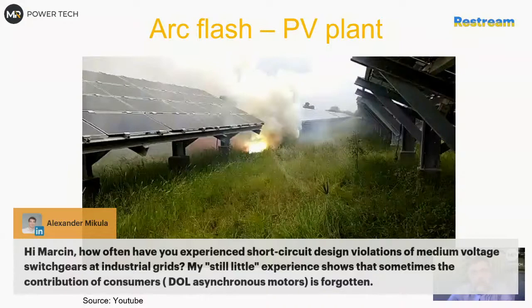On medium voltage, it's not that often - it happens sometimes, but usually they are overrated. A bigger problem might be loading, and sometimes proper protection. I don't see medium voltage issues with short circuit rating that often, but it really depends on the utility grid. Much more I see problems on low voltage.